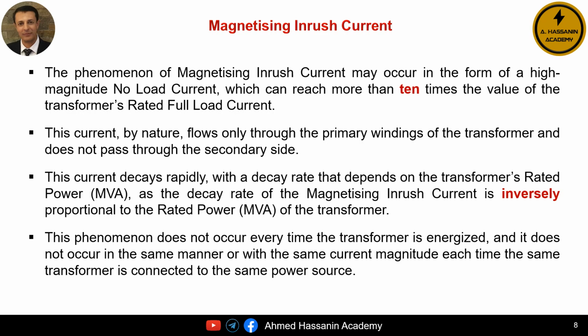As I mentioned earlier, this magnetizing inrush current occurs only in the primary windings, and of course, it decays quickly, with a rate of attenuation that is inversely proportional to the power rating or the rated capacity of the transformer. It is also important to understand that the phenomenon of magnetizing inrush current is a random phenomenon, meaning that it does not necessarily occur every time we energize the transformer. And even if it does occur, it does not necessarily have the same current magnitude, even if it is the same transformer and the same power supply source.